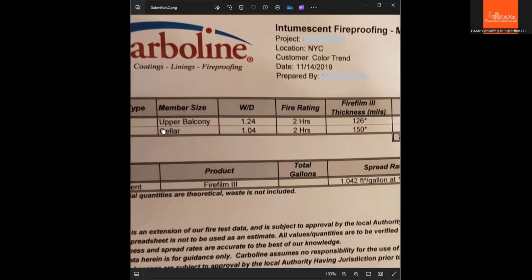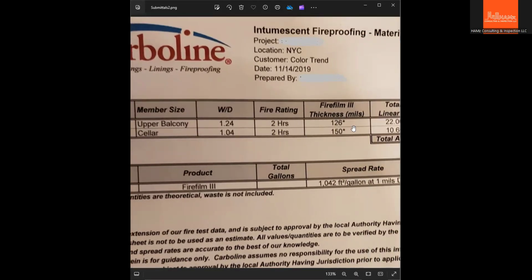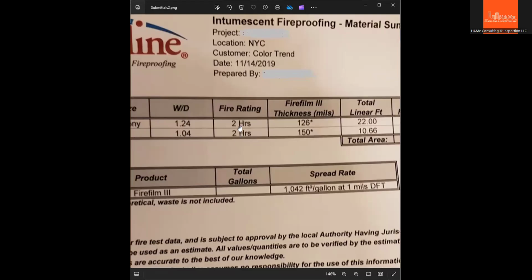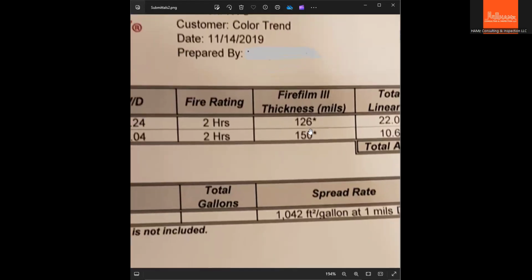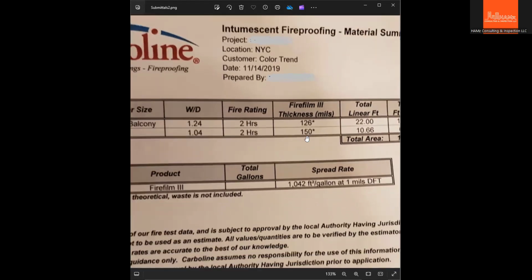So imagine this is the rating now: column, upper balcony and cellar. You got a 2-hour fire rating, and for that to have a 2-hour rating, this is the equivalent thickness. As you can see, this is a lot. It's going to be a lot of thickness to acquire. As you can see, the previous photos I've shown only reach 7 mils, 5.5 mils, or 6 mils. It will take a lot of time, and it depends on the curing. As you can see, 24 hours before they get another coating. Imagine how many coatings this is going to take? 126 mils and 150 mils.